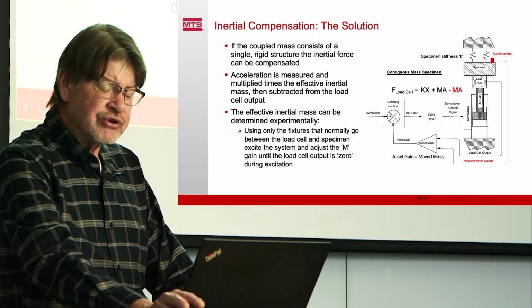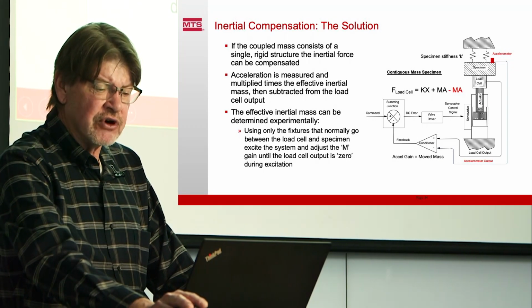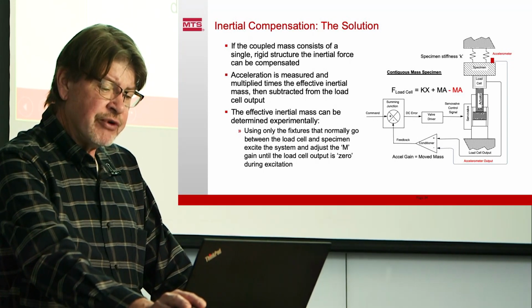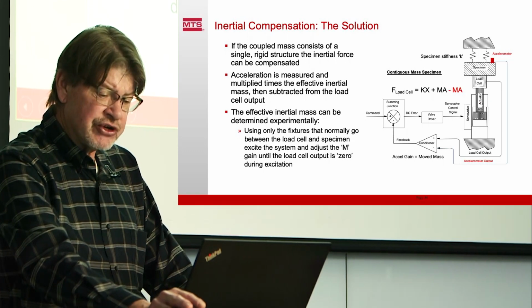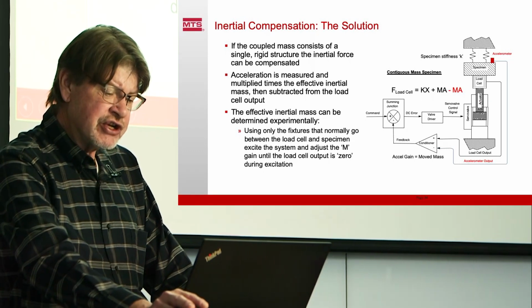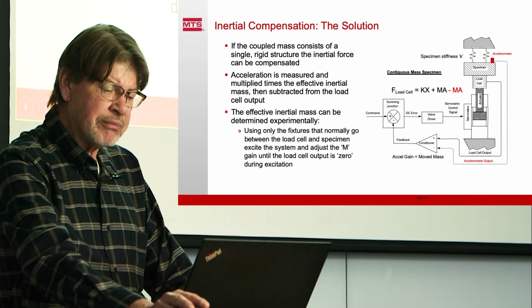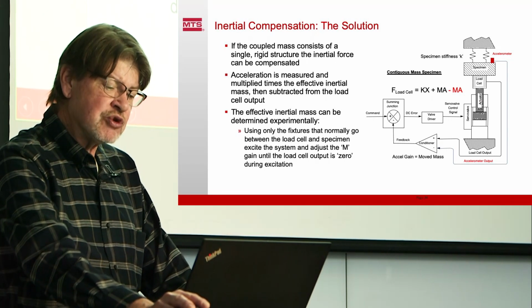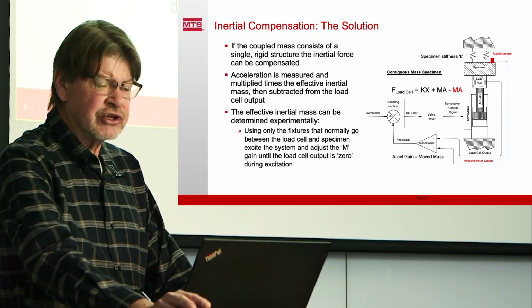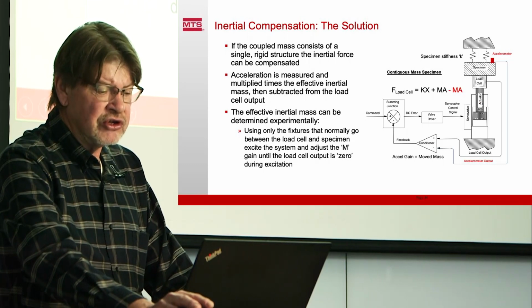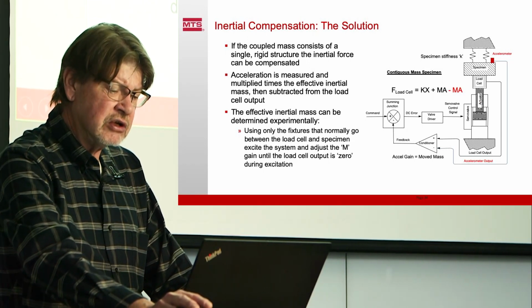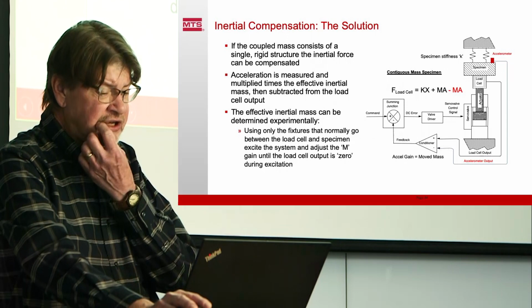So what we really want to do is compensate for that. We want the right force up here at the top. Well, if we add an accelerometer here, we measure the acceleration, and we condition it and multiply it times the effective moving mass. We're effectively subtracting the acceleration or inertial component from the overall load cell signal, and the corrected signal should be more accurate. And that does work.